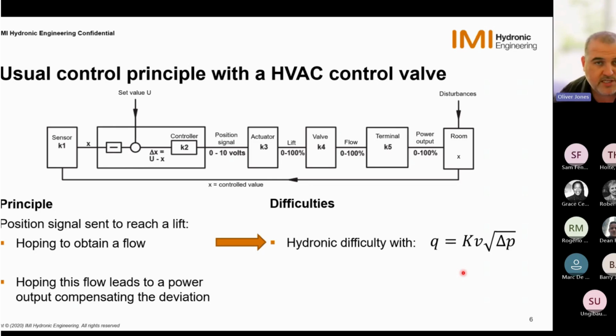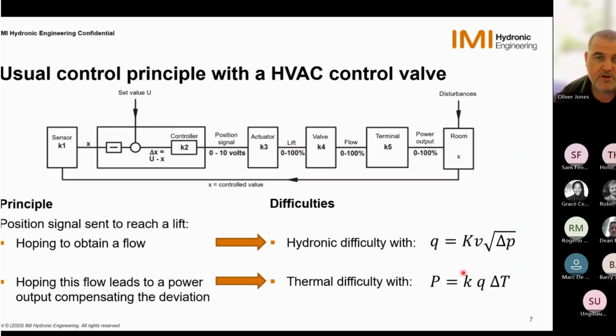But there is another difficulty. Even if I provide a terminal unit with a generous flow, I still might not get any thermal output out of it. So imagine there is a lot of dirt that's clogged into the terminal unit and that's accumulated on the heat exchanger. This will diminish the ability of the terminal unit to deliver a thermal output. So therefore, you might be at the right flow and still not get a good power out of the terminal unit.